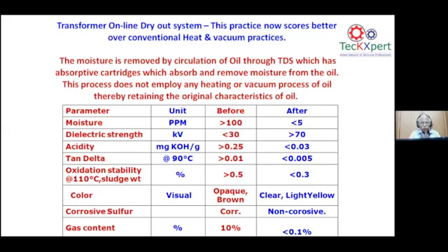You can see the parameters before and after doing this online dry out system. This is going to be the order of the day in the years to come. Definitely this is an add-on system to the existing transformer to maintain the quality and the sustainability of the transformer, especially the transformer characteristics. You can see the ppm has come down from 100 to 5. Also the dielectric strength has improved to 70 from 30.